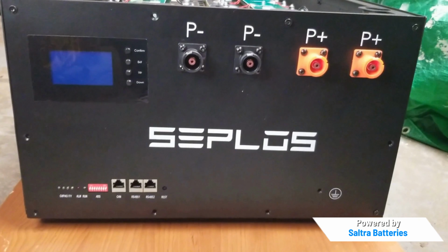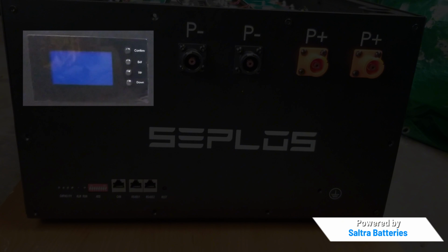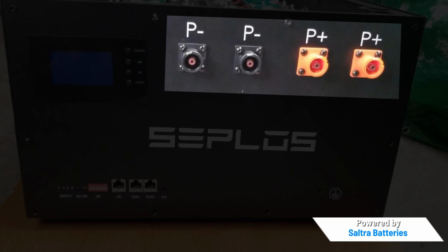This is the complete interface panel. Top left, LCD display. This shows pack voltage, current, SOC, and any warning codes in real time. This is what you'll read every day. Center, 4 power connectors. 2 labeled P- and 2 labeled P+. These are your main output terminals. This is where you connect your inverter cables. The dual connectors allow for higher current capacity and redundant connections.